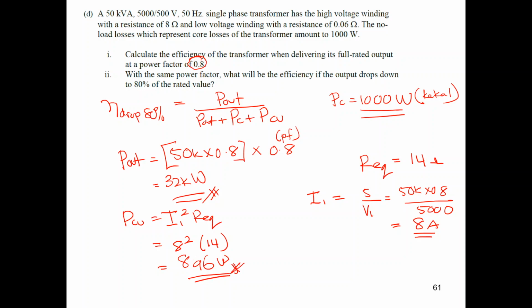896, okay, it's correct. So based on this value, you can find the new efficiency after 80% of the rated value. So P out is 32k over 32k plus 1000 plus 896.